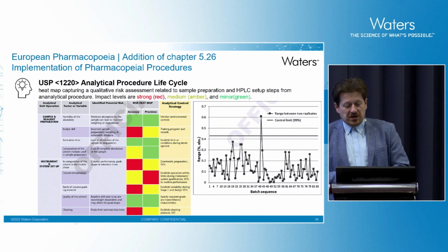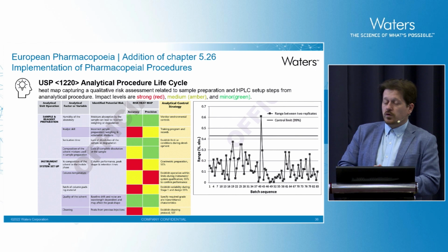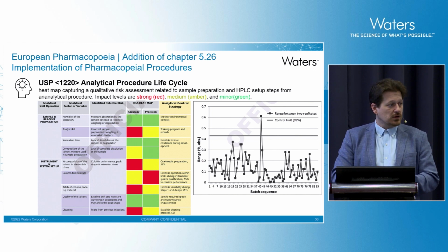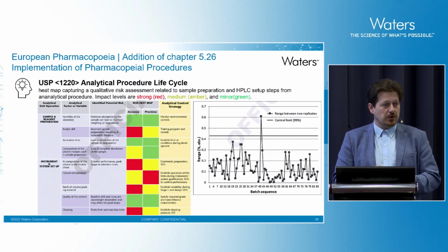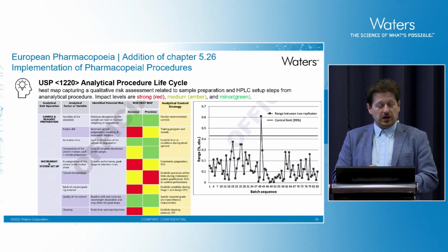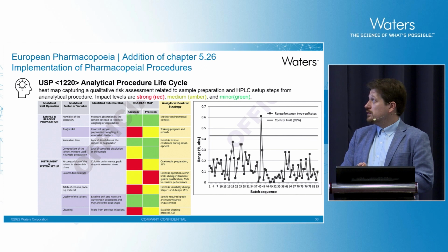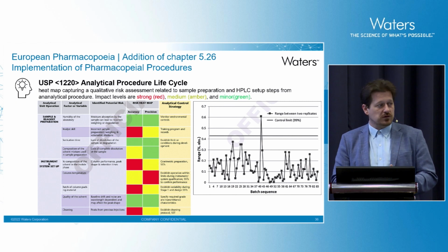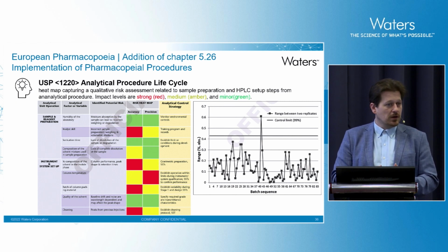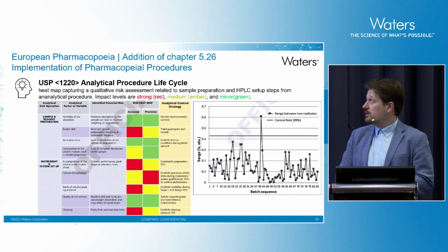When it's about the columns, for all our columns, we also sell so-called QCRMs, Quality Reference Material Standards. We use them in the factory to test our columns before we sell them. You may consider also buying one standard of it, if you like. Reconstitute, aliquot, put in freezer, it will last for a year or more. It lets you check if the stationary phase of the column is still as it was when you got it factory new. This is very important if you are in an R&D environment, if you develop methods, because you must trust that the ligands and the stationary phase were not damaged due to some injections that happened at some time before by someone else or in the recent past.